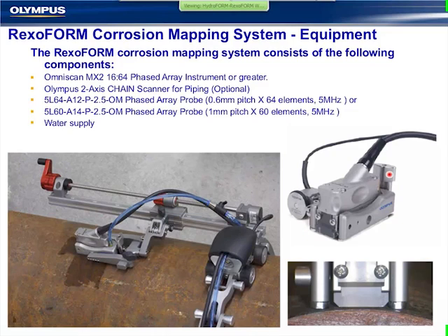So by adjusting this turn knob, it loosens these guides and allows the probe to sit flat and flush, a flat wedge on a curved surface. The wedge footprint has been reduced significantly so that our diameter range is covered with one wedge. And again, this can be put into a scanner, the same chain scanner.